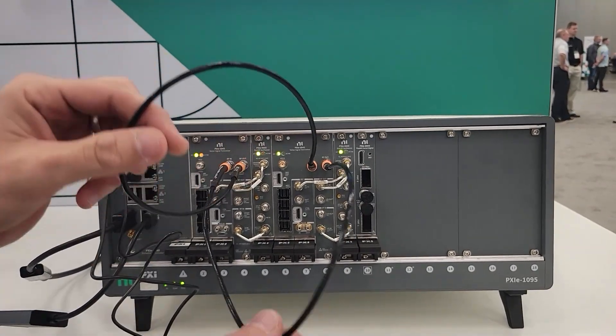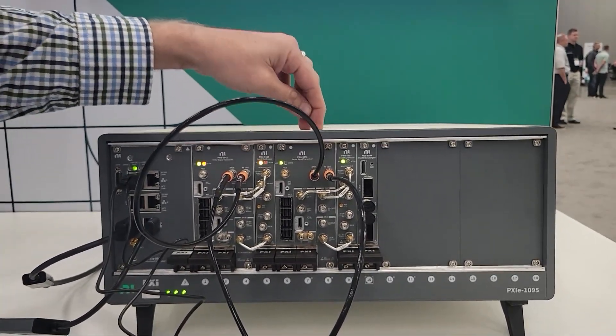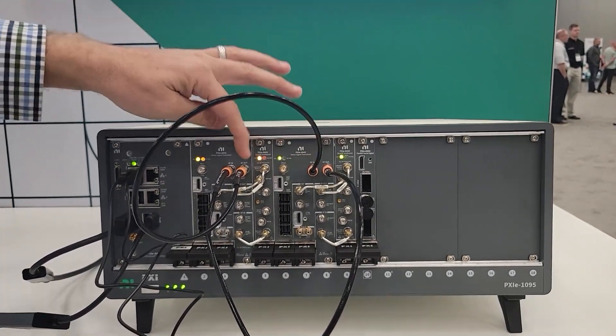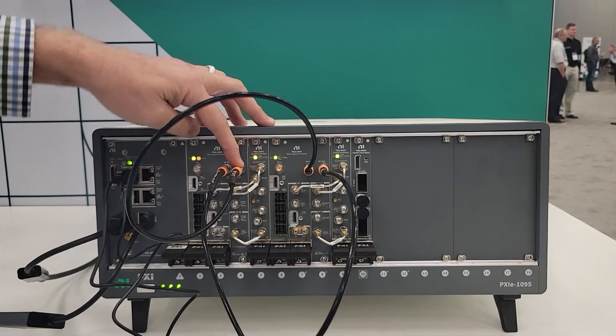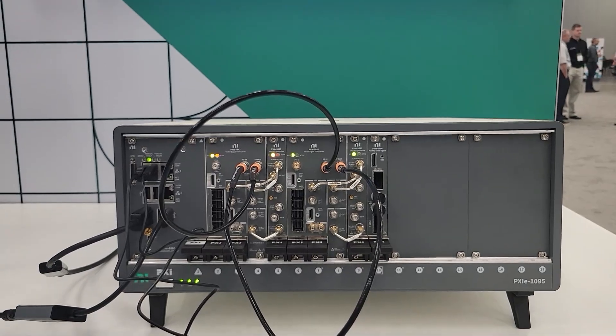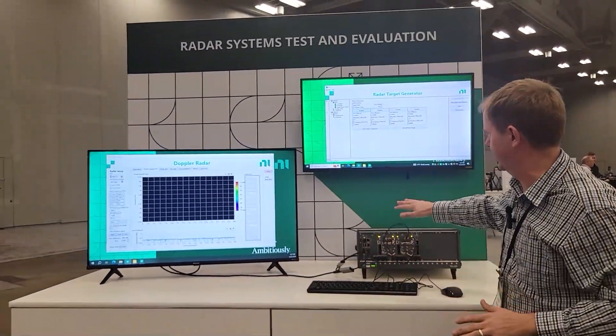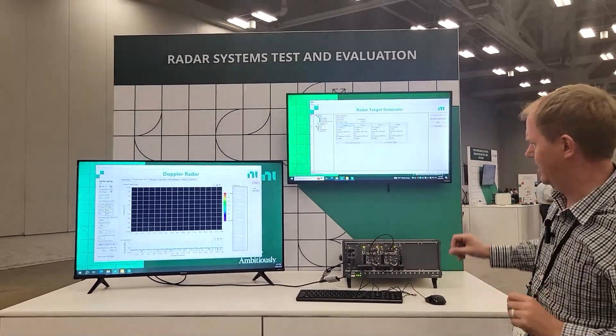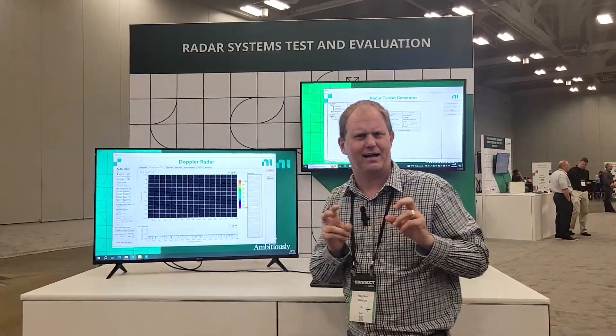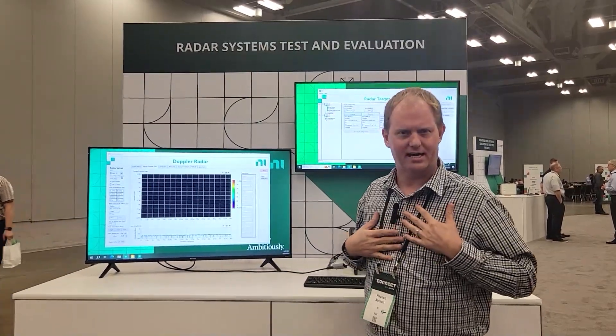You'll see I have them connected with two cables — one of them is transmitting a radar pulse into the other, and then we're applying a target technique for testing, and then we'll transmit the response and look at the output of that RTG target on this vector signal transceiver. Now that you have a good understanding of the hardware, we have our PXI chassis connected up to a couple of monitors. There are two pieces of software. Over here is the radar emulator — I'm emulating a radar. This is more for demonstration purposes; we're not radar manufacturers at National Instruments.